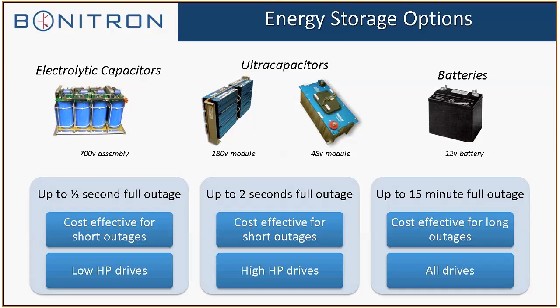Ultracapacitors, 180 volt modules, 48 volt modules. The capacitors are inside these modules. Just connecting them together and making sure they're properly mounted and connected to the DC bus of the drive. As far as the batteries, we can use any kind of battery. The standard is valve regulated lead acid, and there's no special considerations for the batteries as long as they have the cranking amps to take care of what your requirement is for the ride-through.